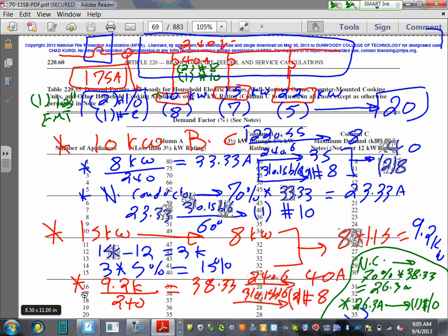Any comments, guys? Any questions? 310.15 B16. So let's put all this stuff again here. This also ends up with, believe it or not, 40 amps. And the conductor also ends up the same size, two conductors number 8. And the neutral was one number 10. Same size. Look at that. They're different sizes, 10 and 15 kW, but they end up with the same size circuit breaker, the same size neutral and the same size conductor, based on the derating.